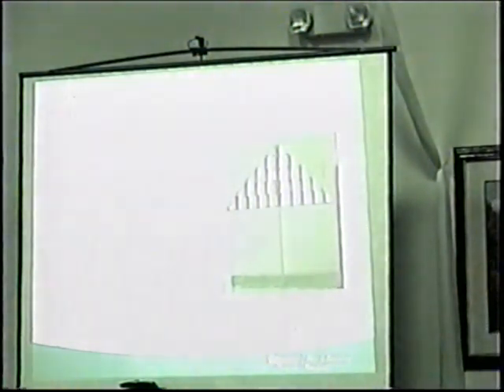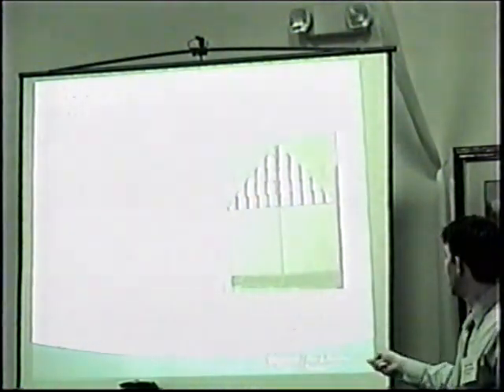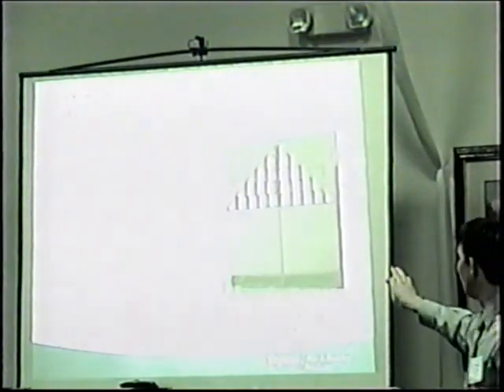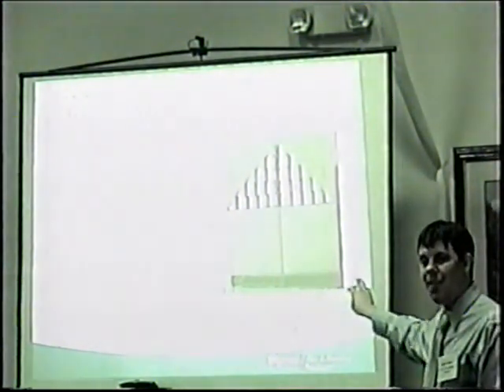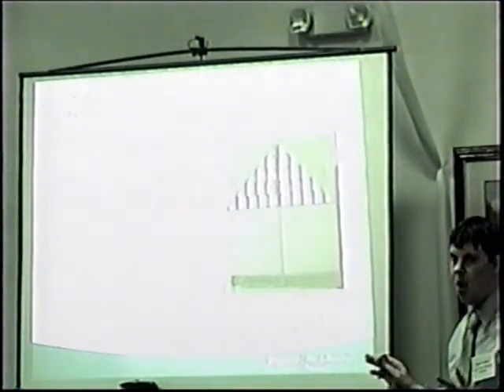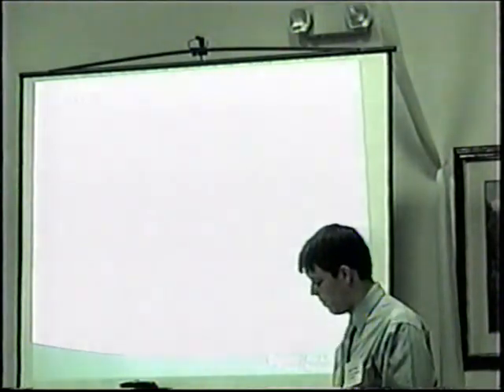The laboratories have decided that this is a class 3 commodity. Well, the test that we use to develop a class 3 curve doesn't have properties that look anything like this. So either this commodity is wrong, or the class 3 curve is wrong, or maybe none of it's wrong and we've just gotten lucky. It's definitely one of those three things. So things get even more interesting when you go to do the class 4 curve.